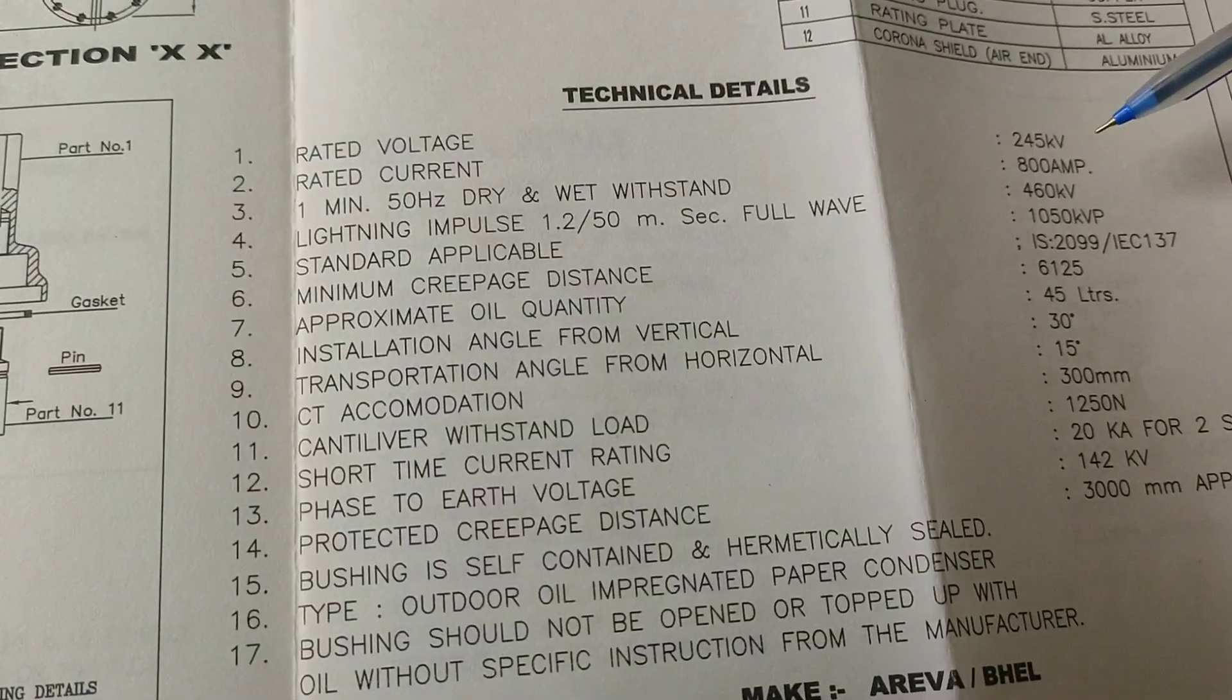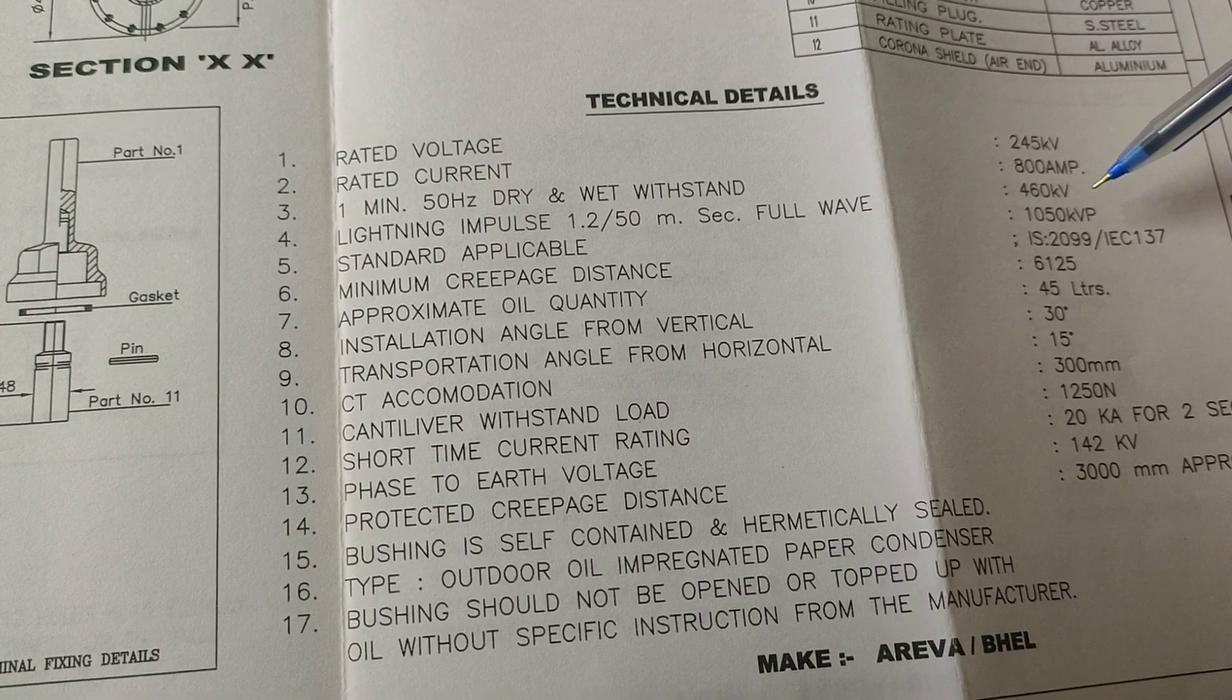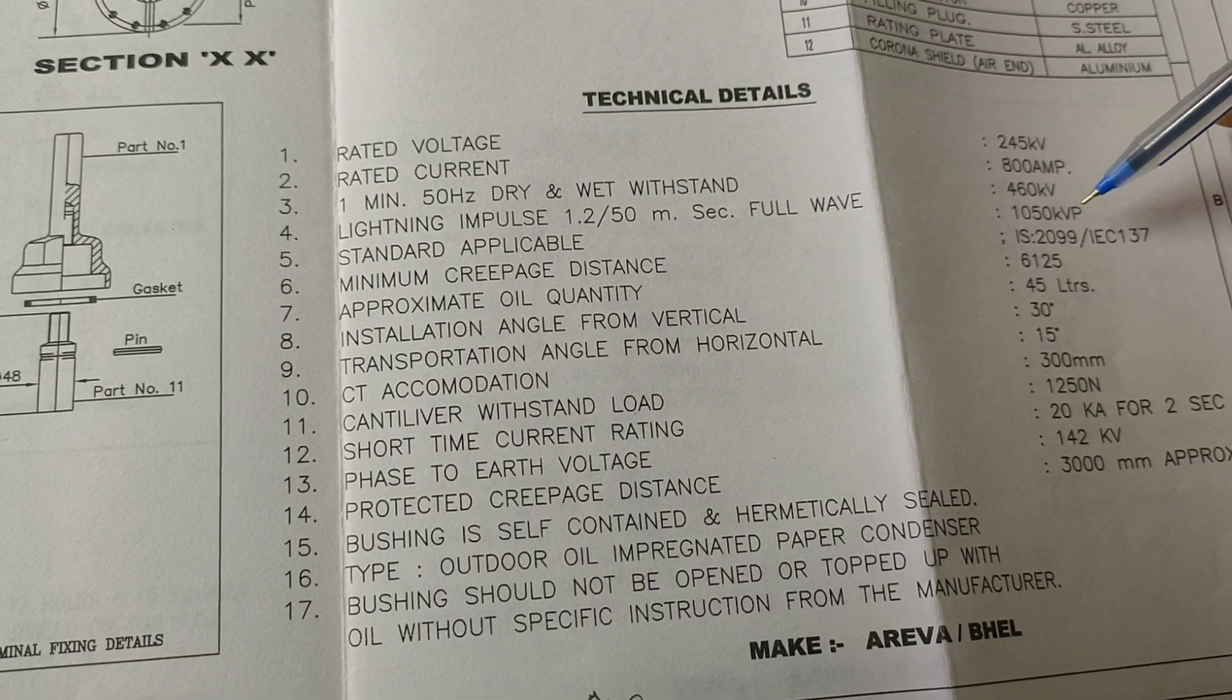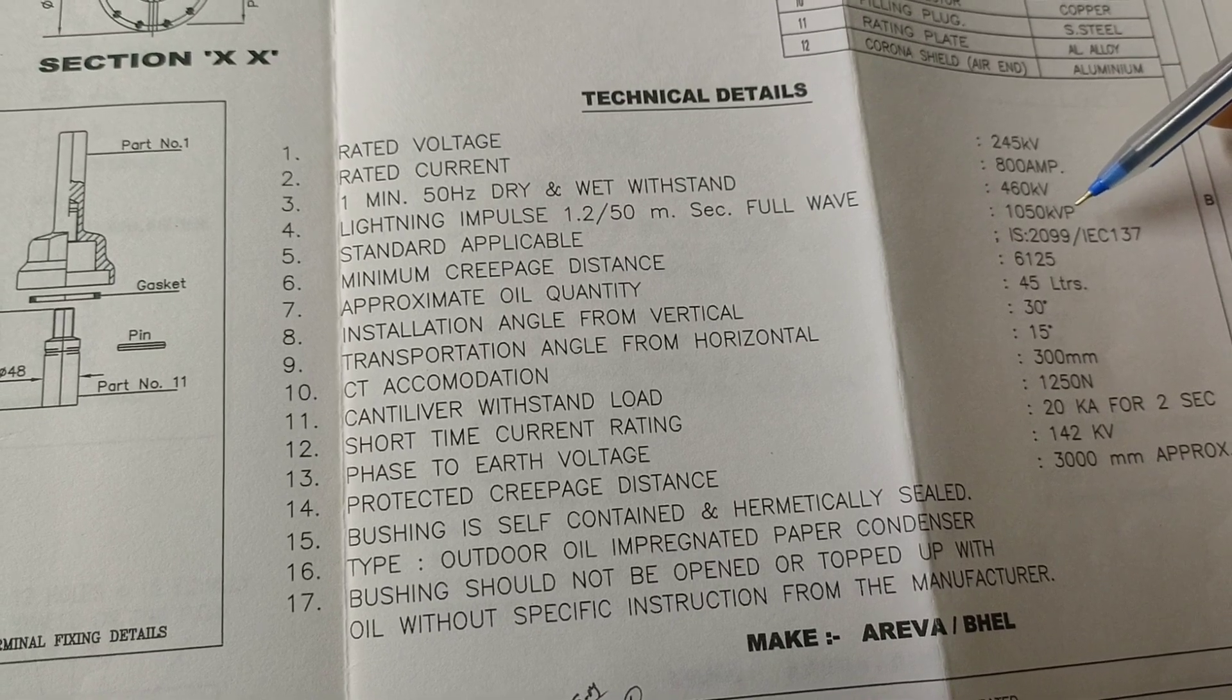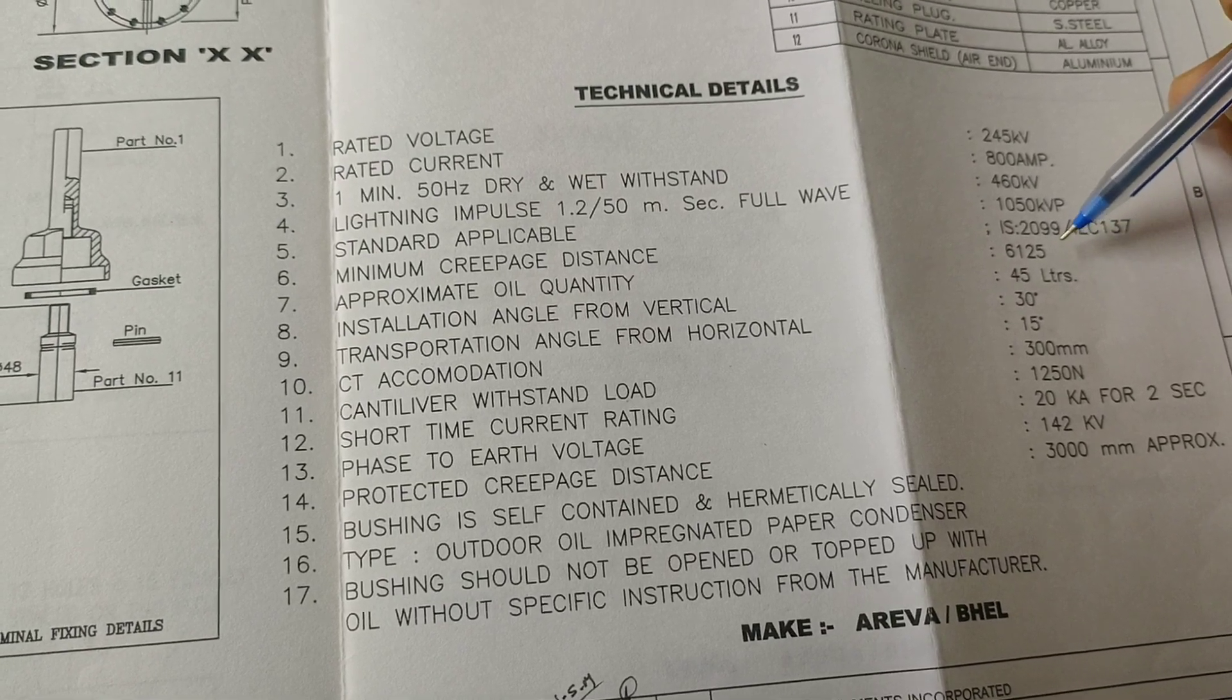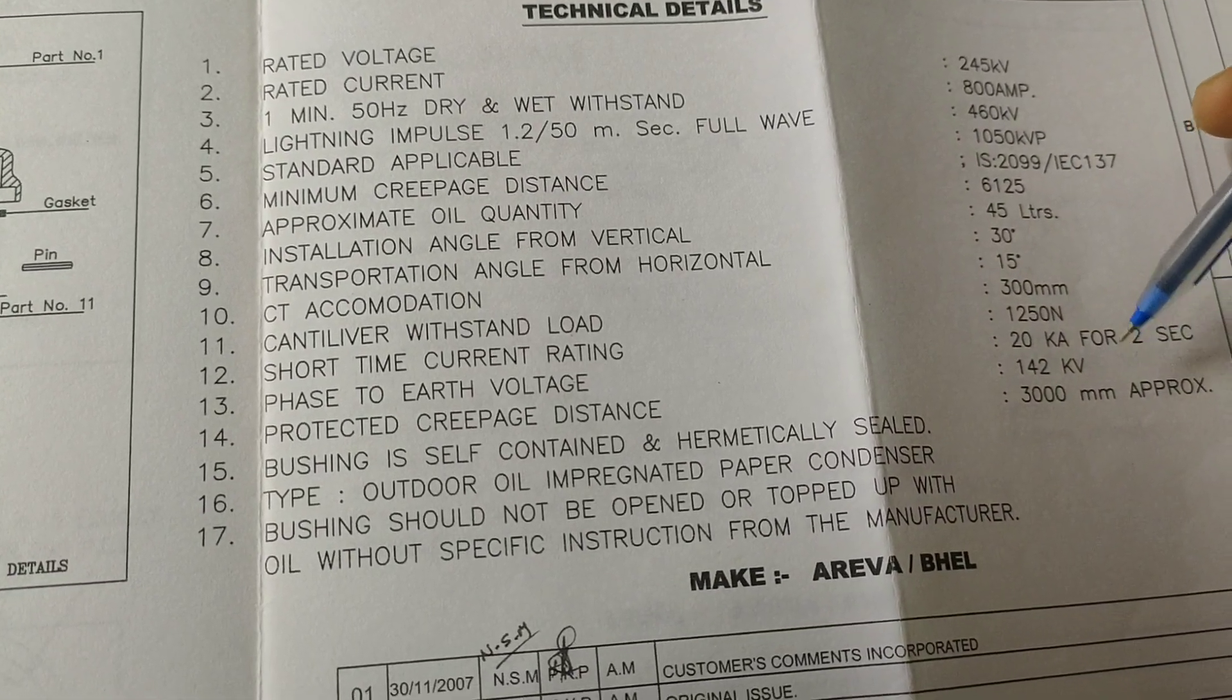The rating of the bushing is 245 kV, 800 ampere. Minimum dry withstand is 460 kV. Lightning impulse is 1050 kV. Here the approximate oil quantity is 45 liters. Minimum creepage distance 6125 millimeters, and the different parameters are here.